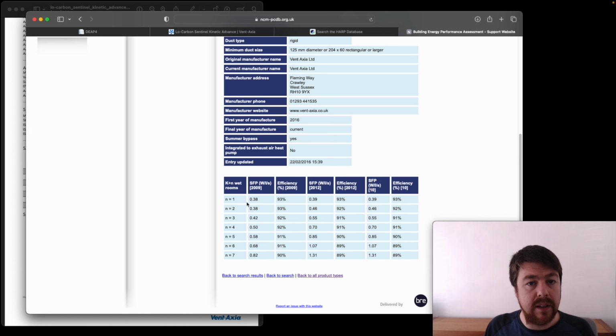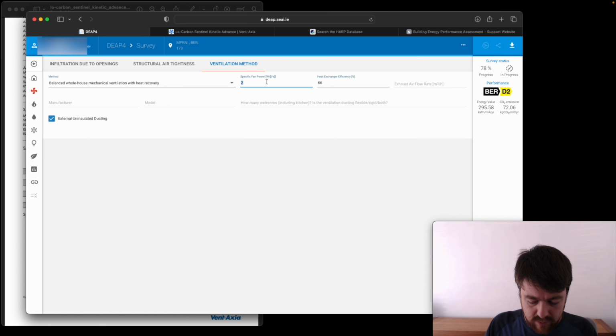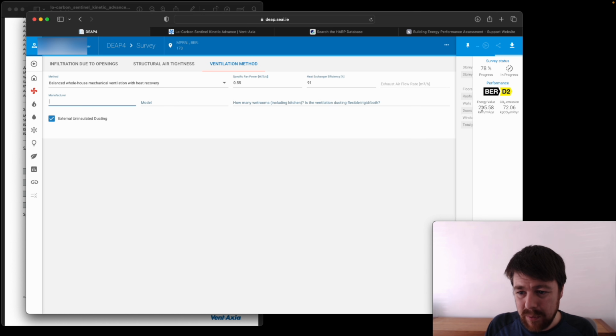So we'll go with N equal to 3. There are different test methodologies over the years; I think we'll use the most conservative number, which suggests per litre per second our unit will consume 0.55 watts, and the heat exchanger efficiency will be 91%. Let's put that into the app and see what it does - 0.55 and then 91 - and see if that improves our numbers.